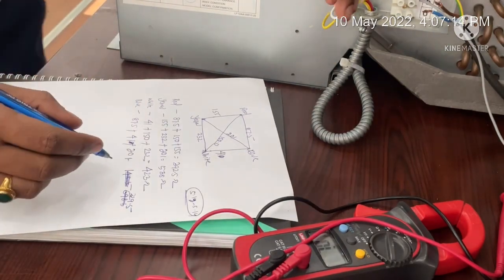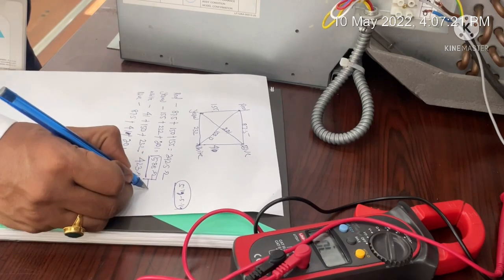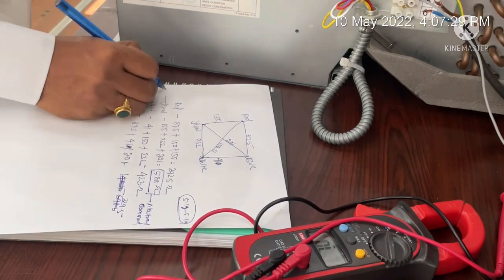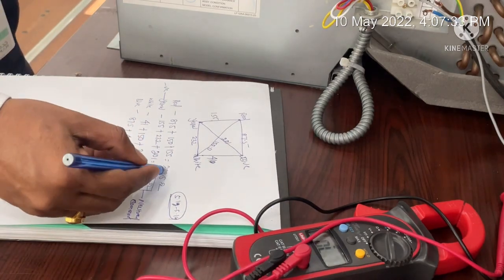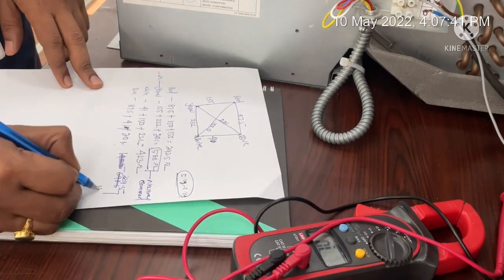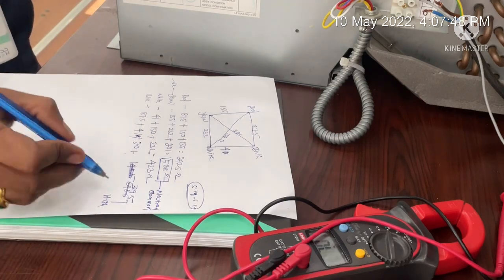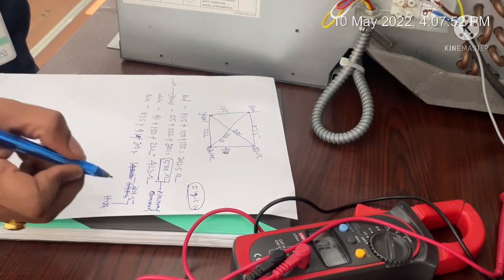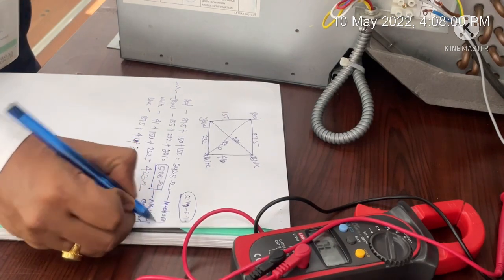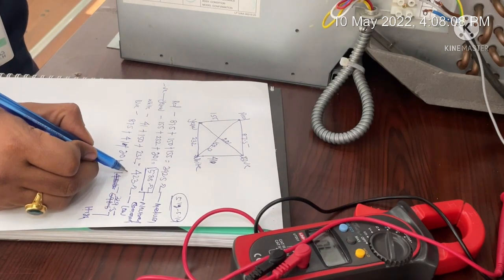The highest total resistance value is yellow at 588 ohms, so yellow will be the neutral cable. Among red, white, and blue — the lowest resistance is blue at 329.5 ohms, which means blue will be the high speed cable. If resistance is high, current flow is low; if resistance is low, current flow is high. So blue is high speed, red is medium speed, and white — at 423 ohms — is low speed.